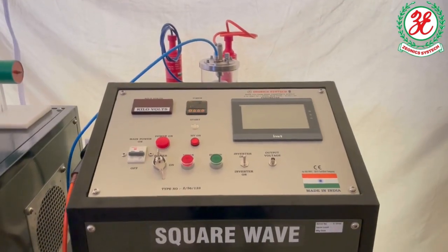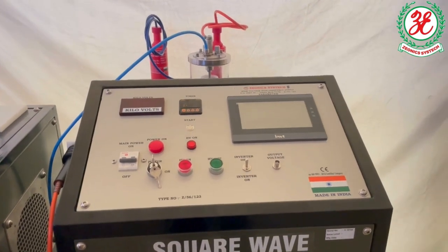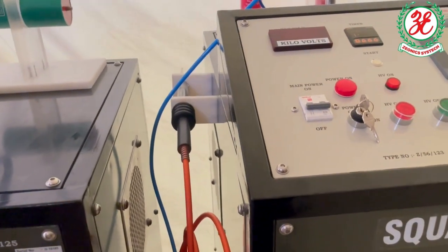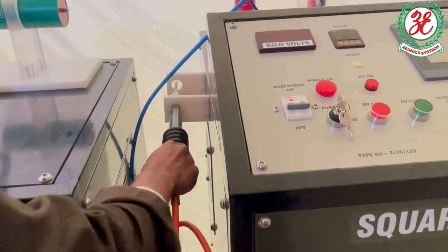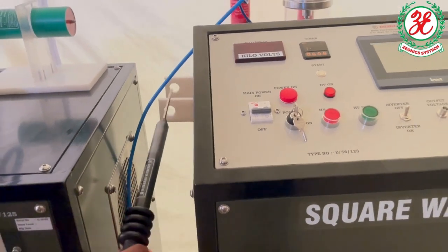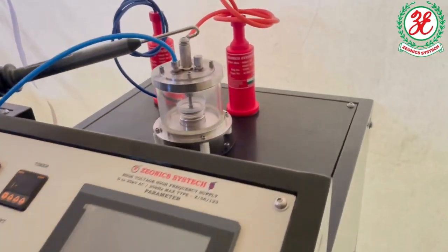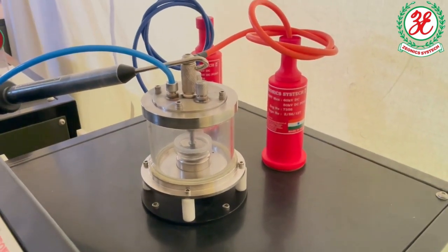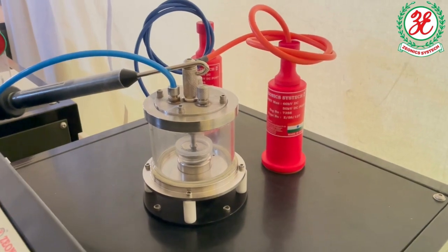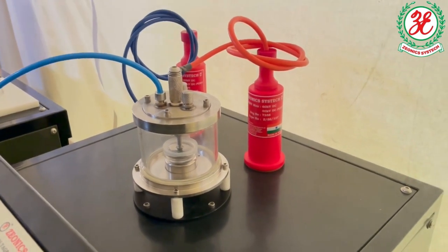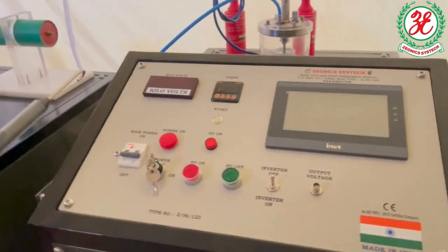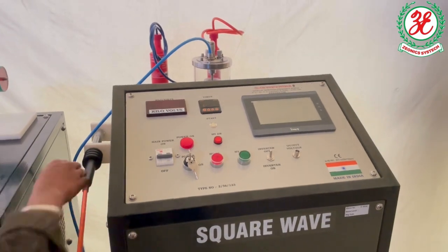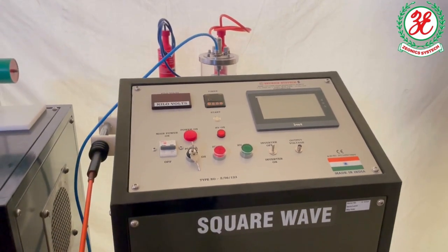For any system, to completely ensure there is no voltage before we touch the chamber, we have a discharge stick available. We will pick it up. It is already connected to ground. We hook it to the high voltage connection. We place it back in its position. Now you may freely touch the plasma chamber.